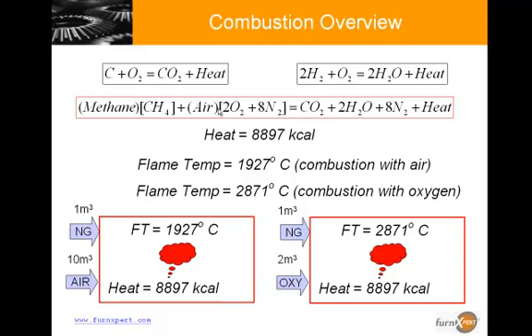However, they absorb heat and reduce the flame temperature. During perfect combustion if methane is burnt with oxygen it produces a flame temperature of 2,871 degrees. Using air with methane produces flame temperature of about 1,927 degrees centigrade. The picture below gives an overview of combustion of natural gas with both air as well as with oxygen.